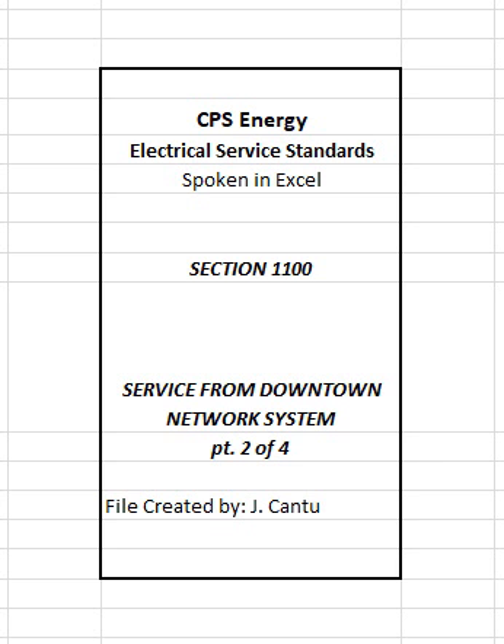2. The transformer vault or room floor shall be pitched toward the sump hole with a 1-inch slope. 3. The sump hole shall be located directly below personnel entrances unless otherwise specified by CPS Energy. 4. The transformer vault or room design shall be such that it does not allow intrusion of water through walls, floors, ceilings, joints, and all penetrations. In some cases, waterproofing may need to be applied.